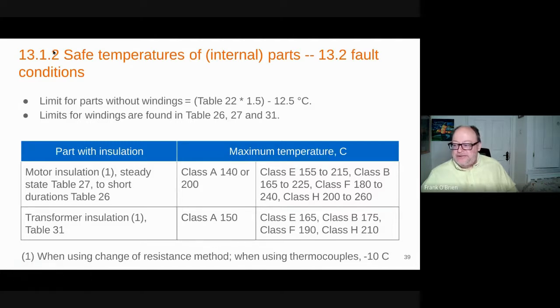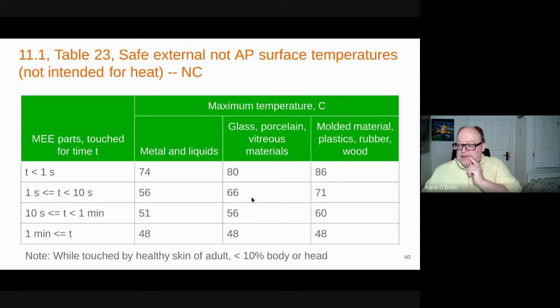All right, and then there's surface safe temperatures, internal parts, fault. Okay, so we're still talking about transformers and capacitors and things. But in single fault, this is the motor transformer stuff. And so we can be hotter because presumably it's less time. This single fault probably resulted in a fail-safe, a stoppage, although not necessarily, it could be impedance protected. Anyway, these temperatures are allowed. All right, and then moving on to surface temperatures, table 23 and 24, we kind of took a peek at.